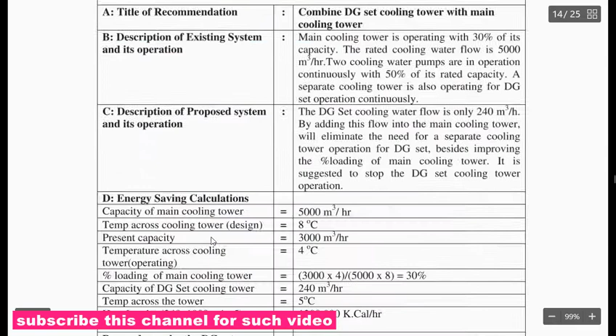And according to the report format for energy conservation recommendation, title of the recommendation: combined DG set for cooling tower with main cooling tower. Discussion of existing system and its operation. Main cooling tower is operating with 30% of its capacity and rated cooling water flow is 5000 meter cube per hour. Two cooling water pumps are operating continuously with 50% of their rated capacity. A separate cooling tower is also operating for the DG set continuously.